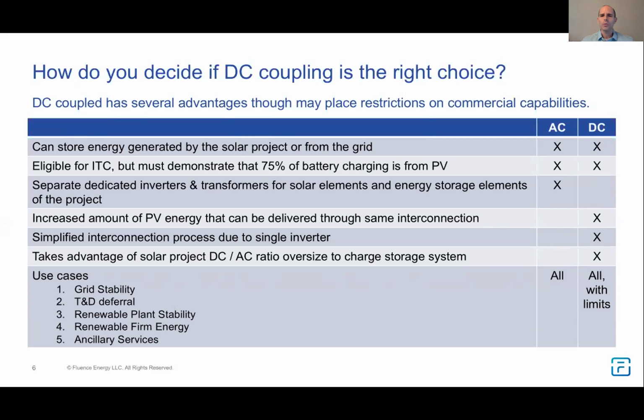One thing common between both, but worth touching on more, is that you can do all of the use cases—grid stability, T&D deferral, renewable plant stability, et cetera—with either an AC or a DC coupled system. But when you DC couple the system, you do limit yourself in flexibility to some degree. I agree with Vikas that you do have some limitations on the use cases and on your flexibility when you do DC coupling.